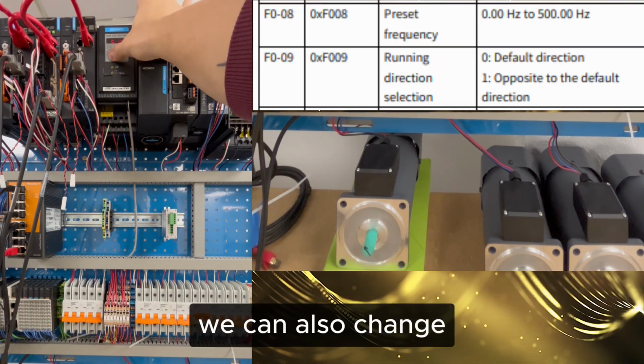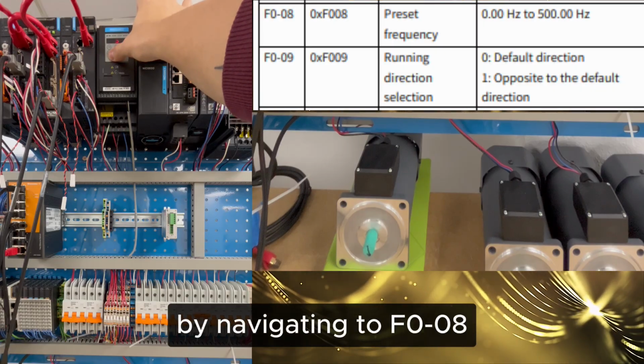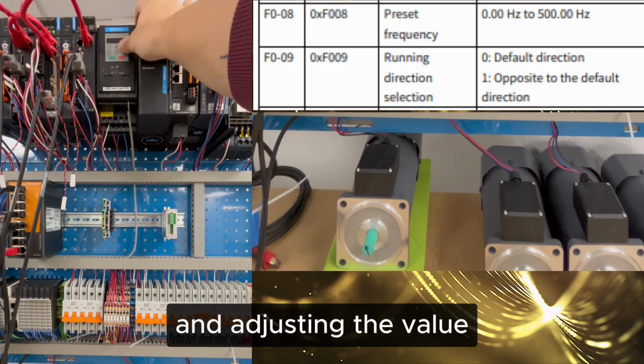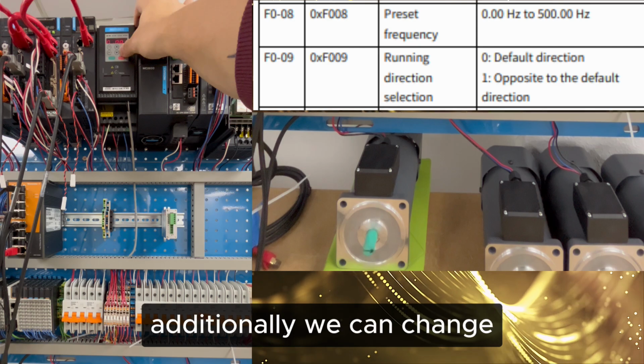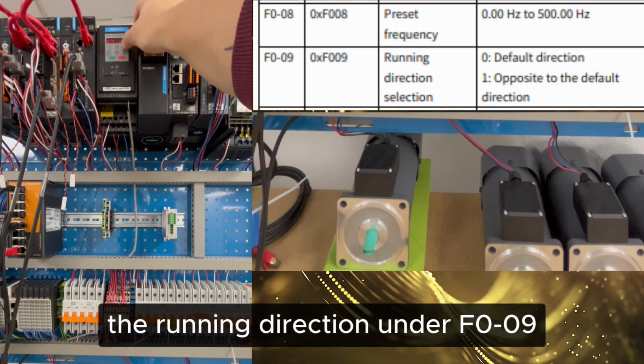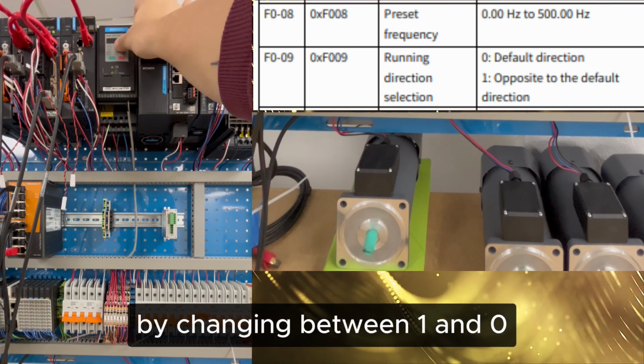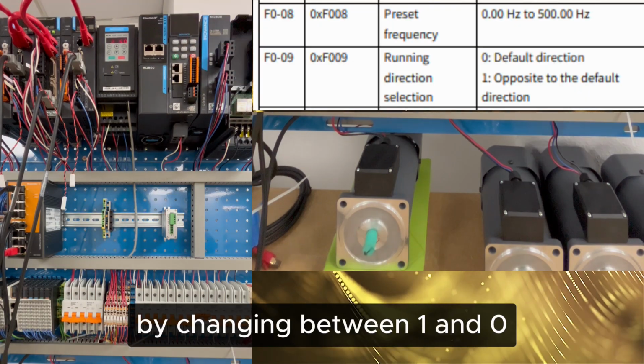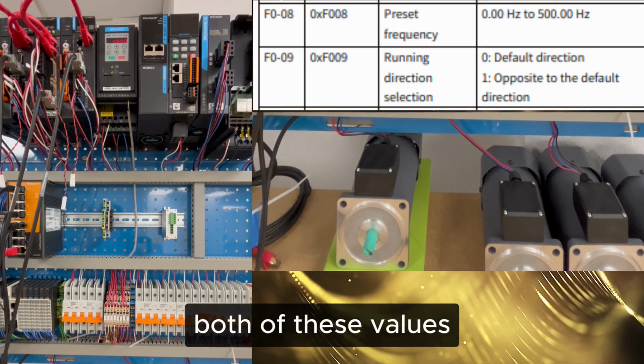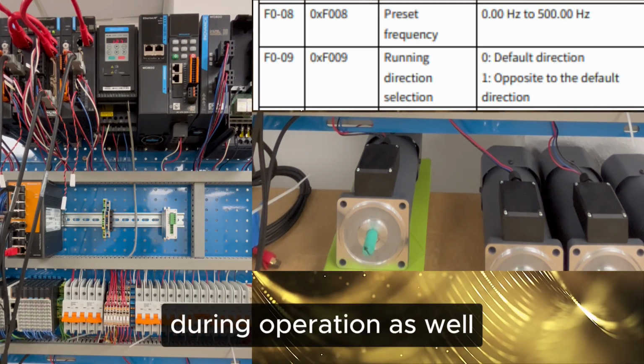We can also change the running frequency by navigating to F0-08 and adjusting the value. Additionally, we can change the running direction under F0-09 by changing between 1 and 0. Both of these values can be changed during operation as well.